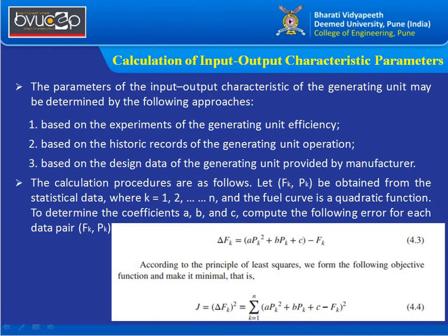The parameters a, b, c can be obtained from: experiments on generating unit efficiency; historical operational data (most commonly used); or design data provided by the manufacturer, which may change with operational conditions. Let fk and pk be obtained from statistical data, where k ranges from 1 to n depending on the power output samples, and the fuel curve is fitted as a quadratic function.